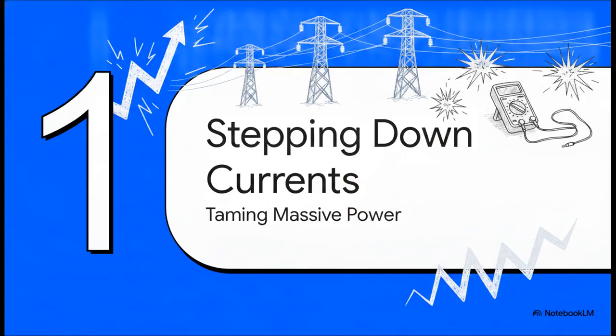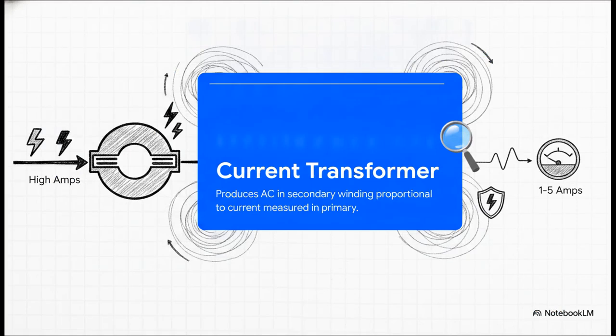Okay, let's jump right into Section 1, stepping down massive currents. So, our journey begins up on those high-voltage transmission lines. Trying to measure that current directly, it's basically physically impossible. If you hooked up a standard lab meter straight to a city power line, it would literally vaporize in a millisecond. To get around this, engineers use what's called a current transformer, or a CT.